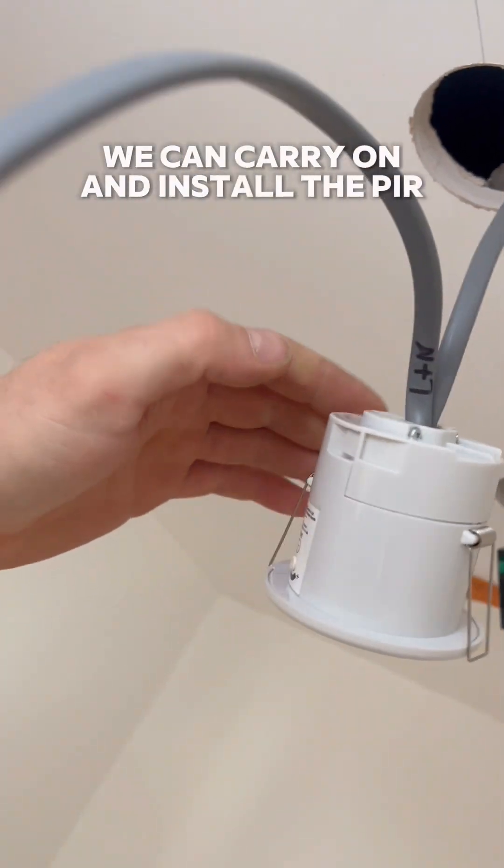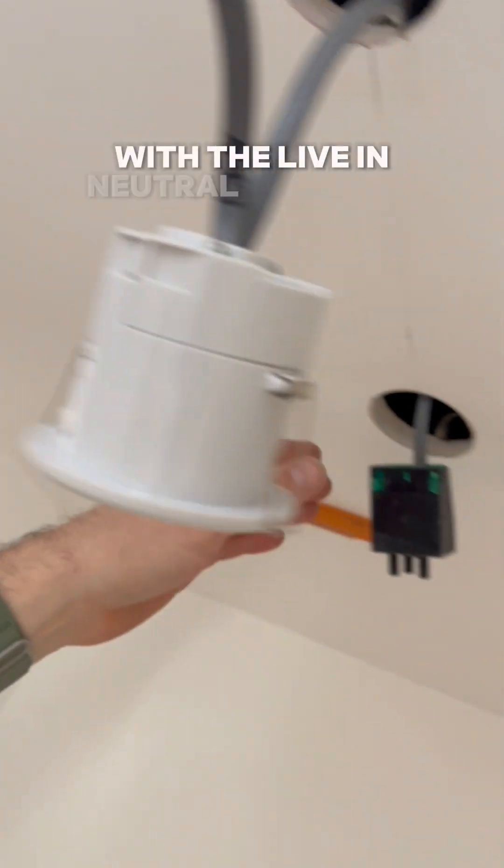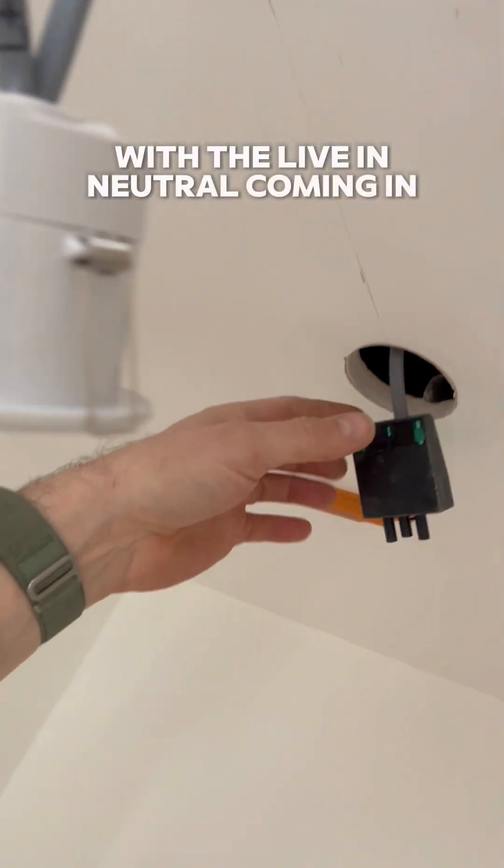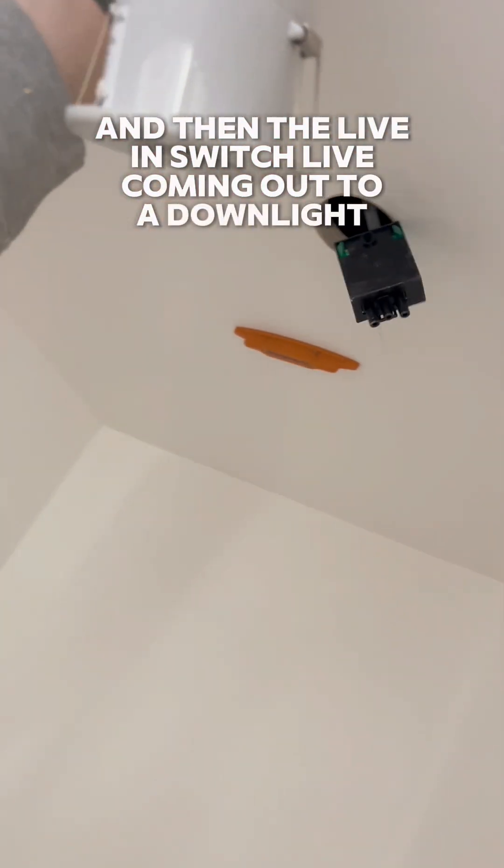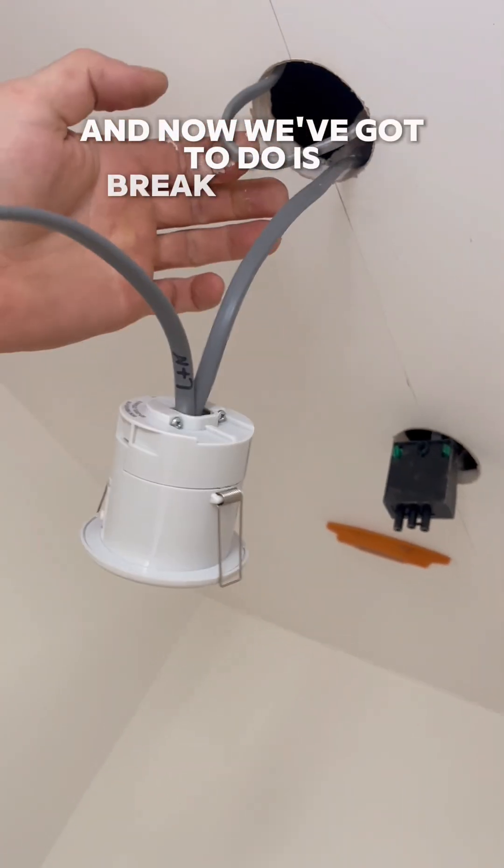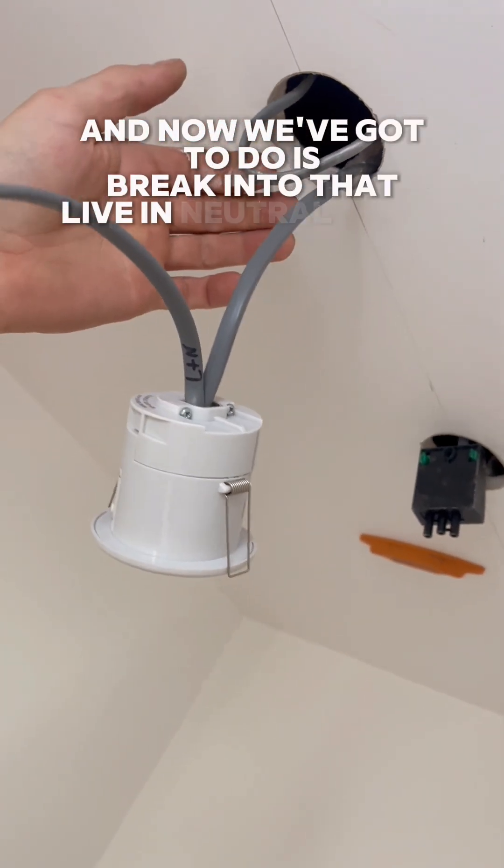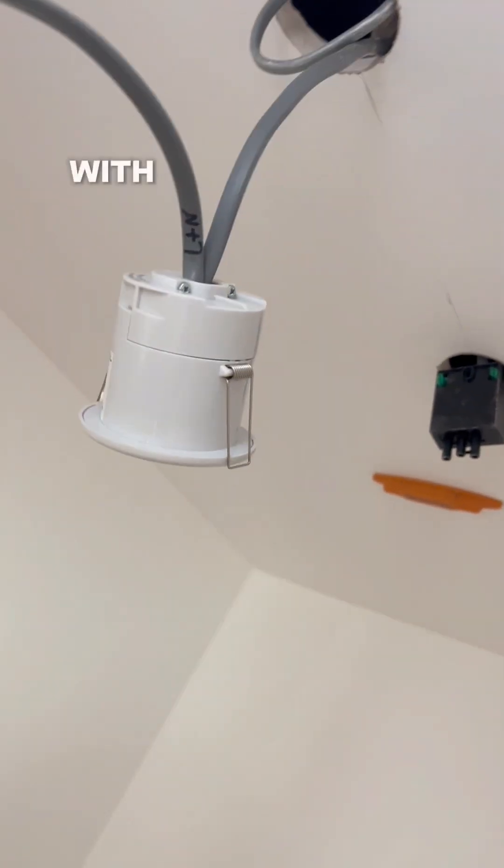With the live and neutral coming in and then the live and switch live coming out to a downlight. And now we've got to do is break into that live and neutral there with a junction box.